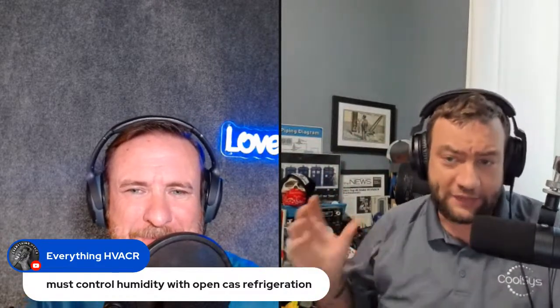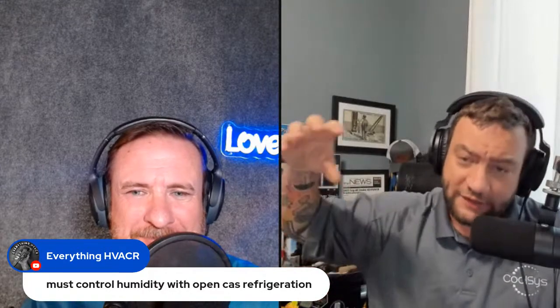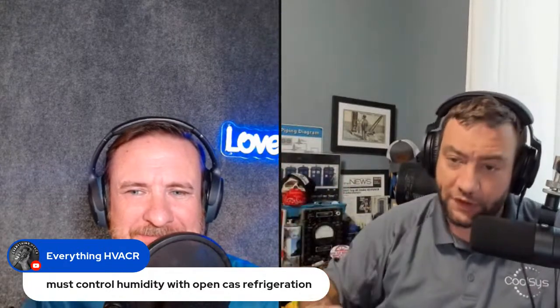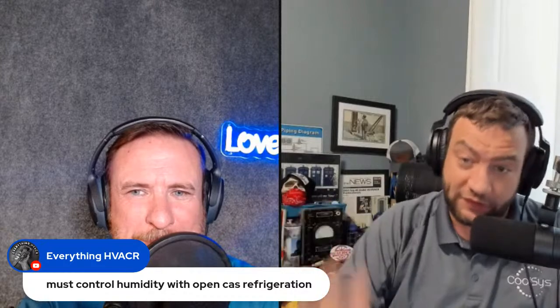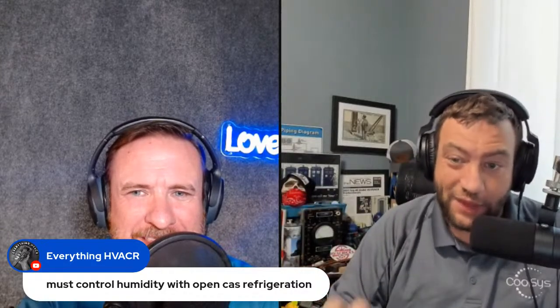It takes straight air from outside, dehumidifies or pre-cools it first, runs it through a desiccant wheel, which brings the dew point down to negative 88, then runs it through a reheat to get the dew point to the set point, I think 16 degrees. So it's dry. They do a whole bunch of production with different CBD powders and stuff, so it has to be really dry, otherwise the stuff clumps together.